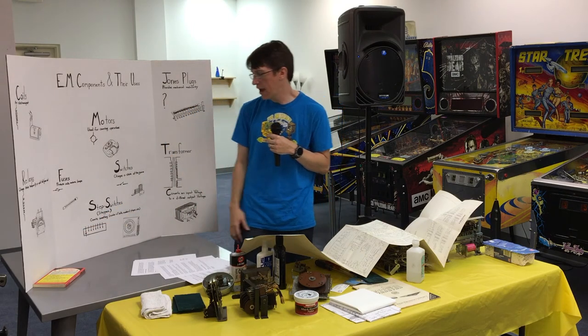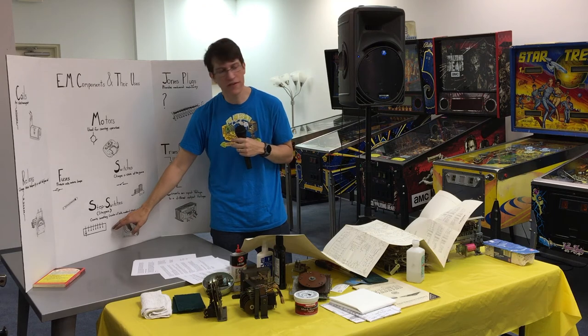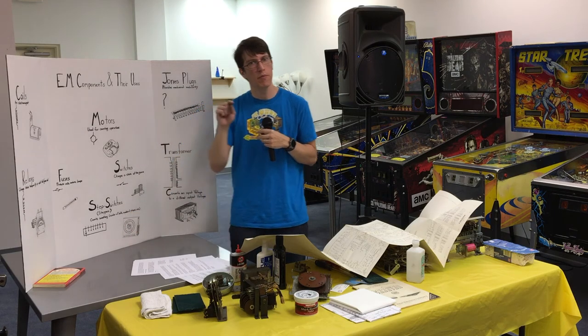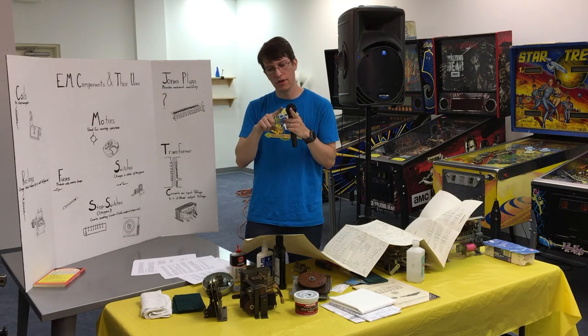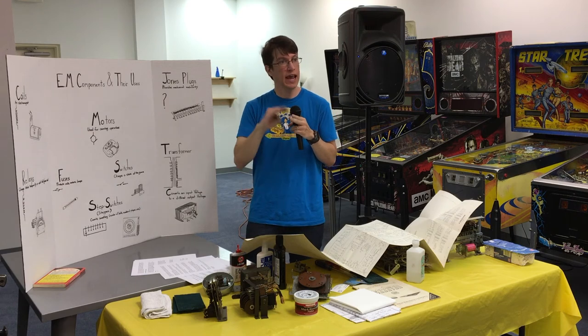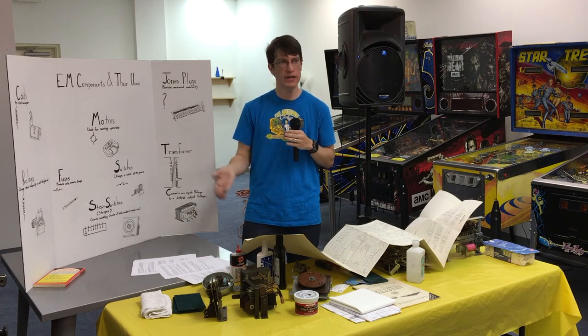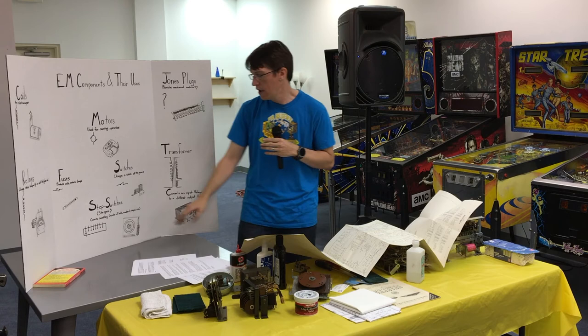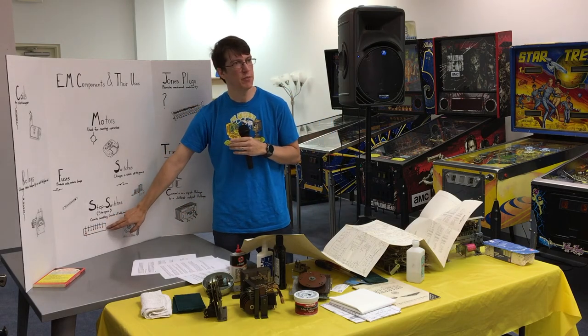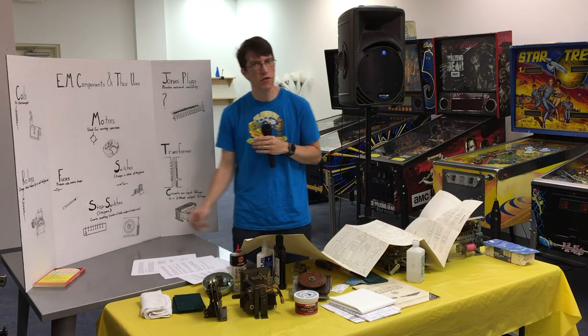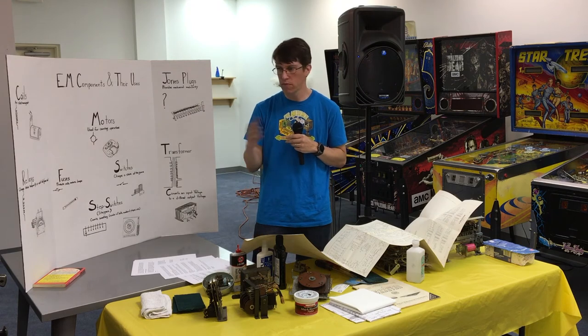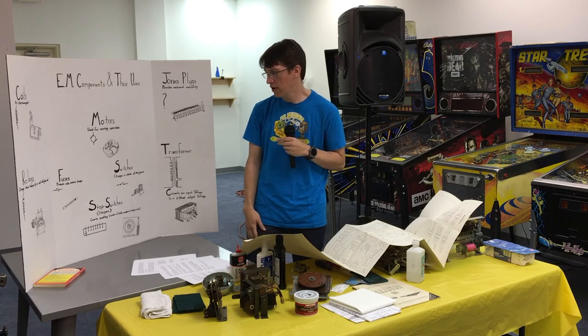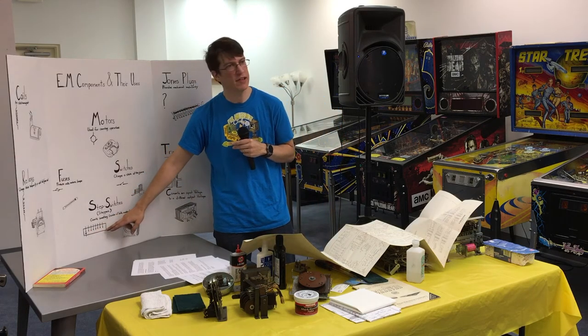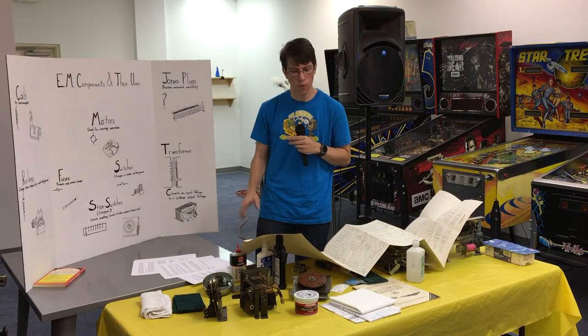So let's say you have a 20-step unit, but every 10 steps the connections repeat. Mechanically you have 20 steps, but electrically you only have 10. On the schematic, it's only going to be drawn as 10. So you may have an intermittent problem where every 11th step, something doesn't happen that's supposed to. The only way you could find that out is by testing continuity from one piece to another.